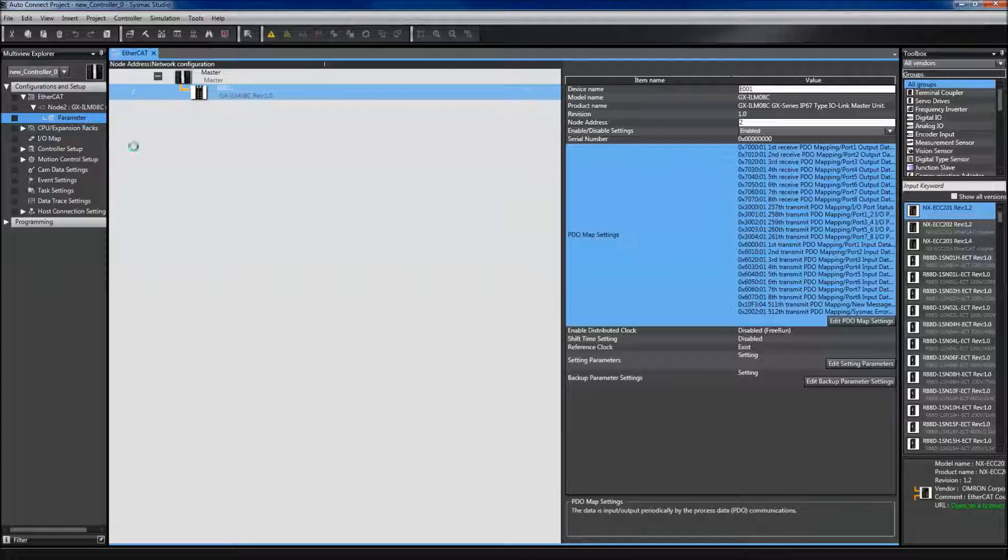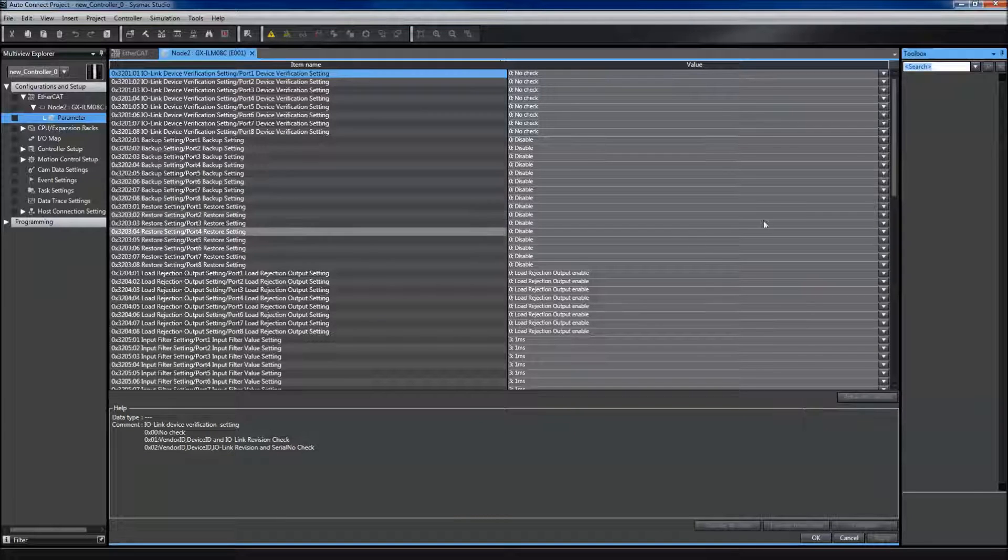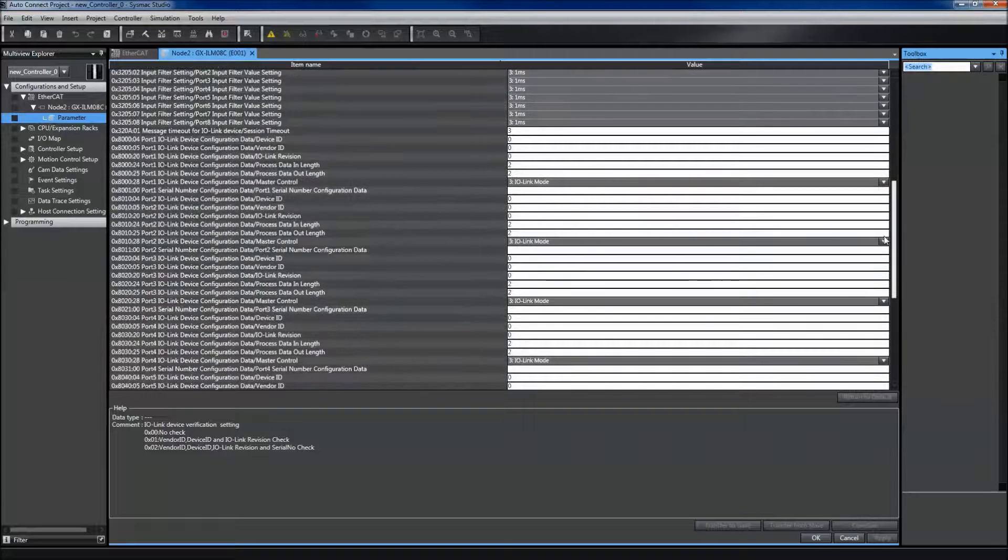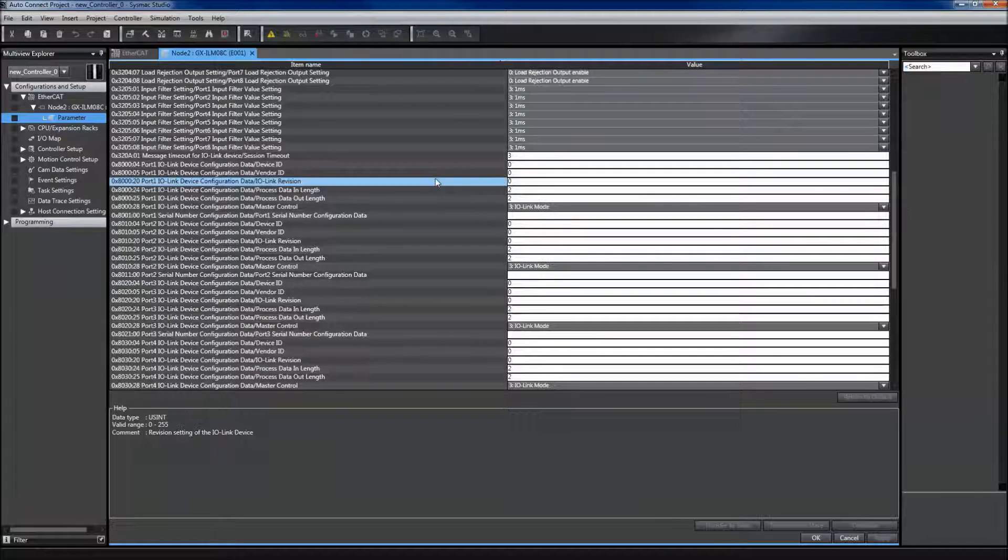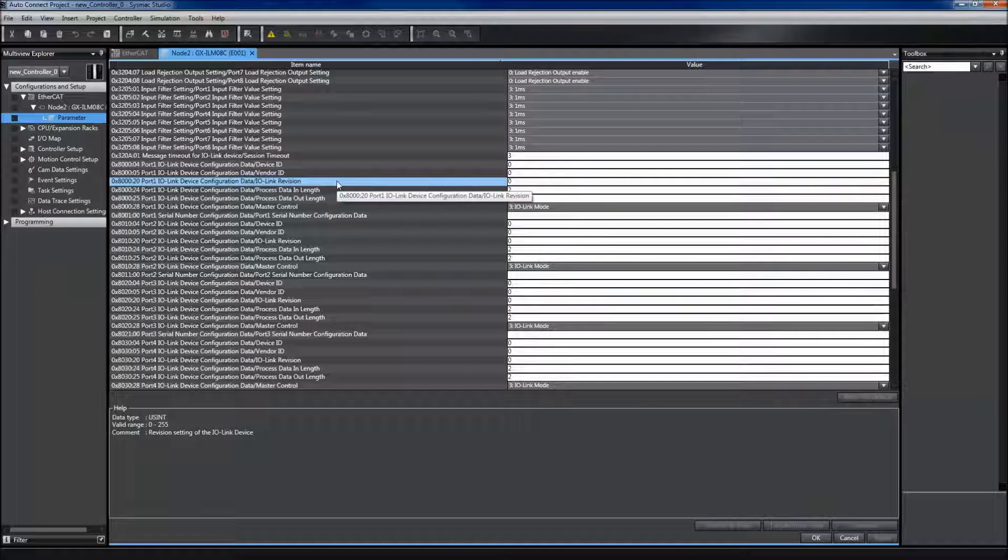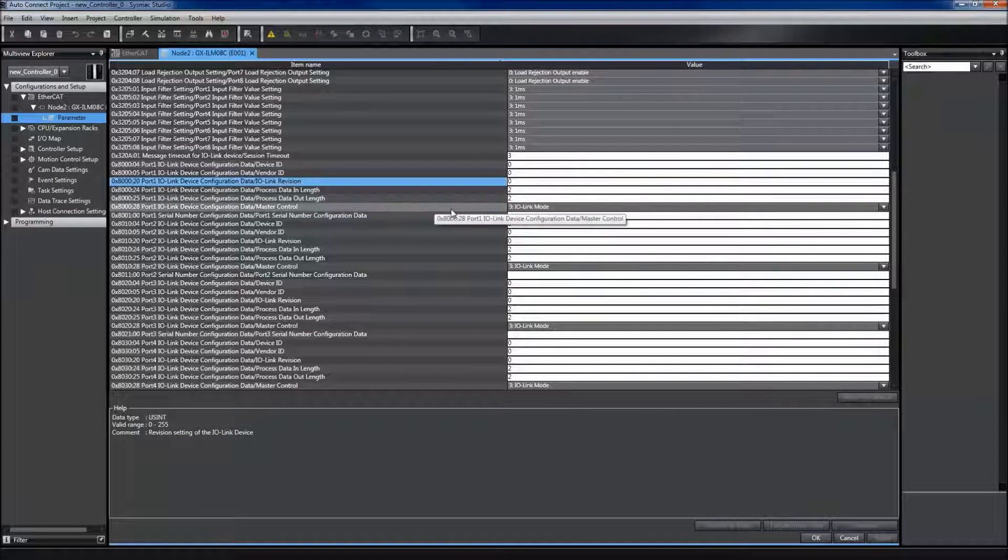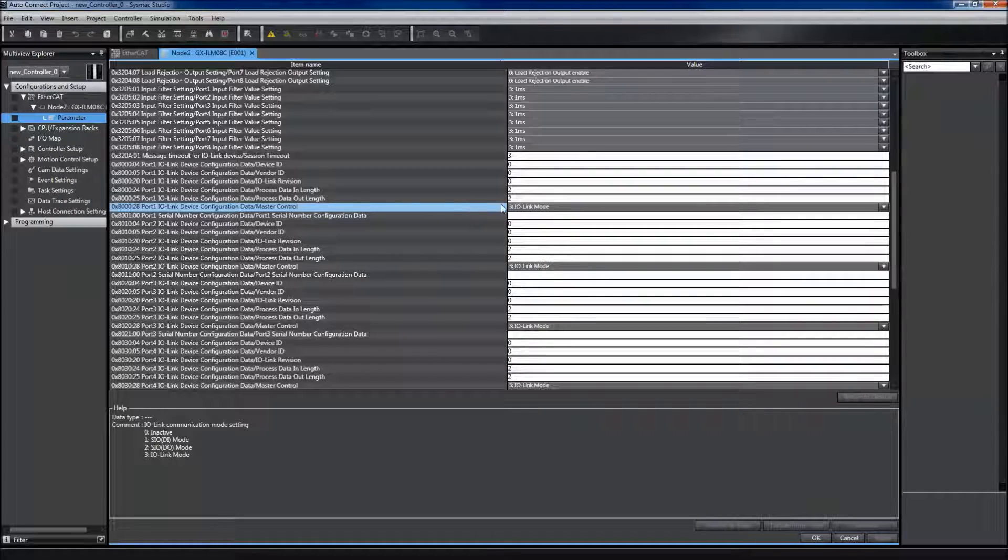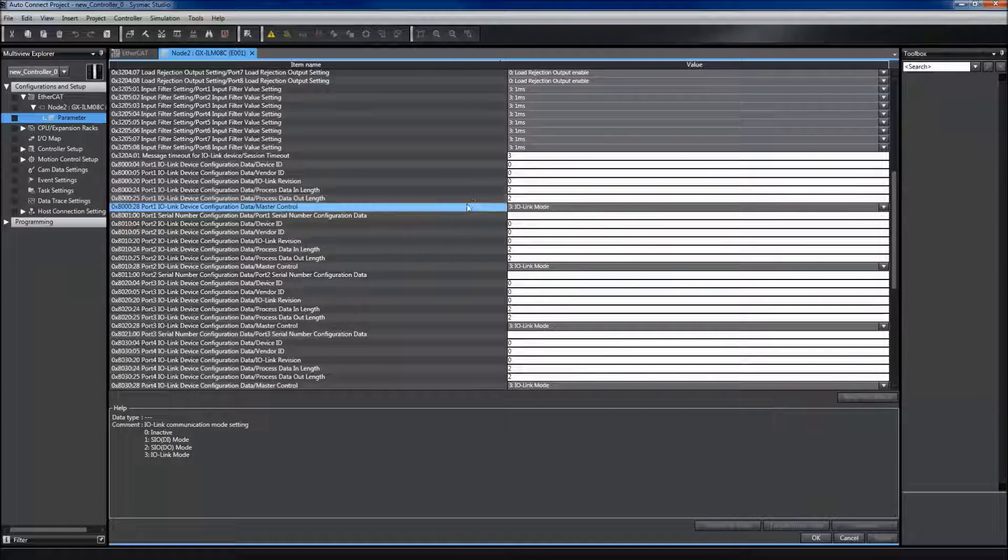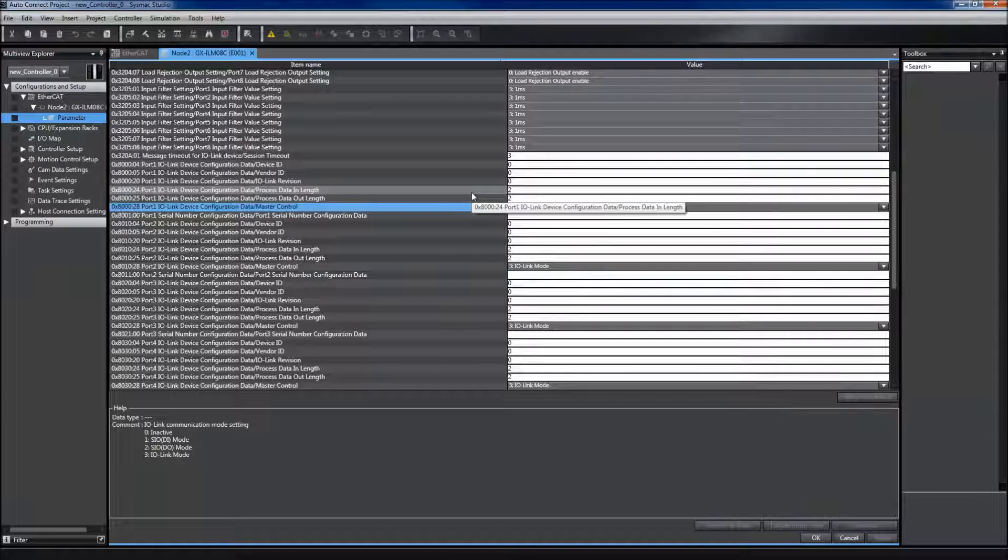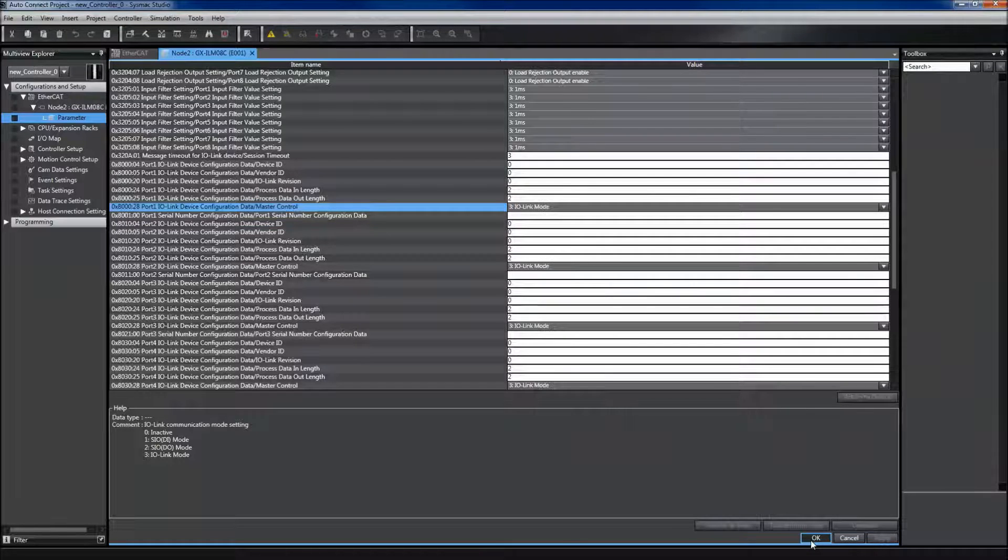I also need to double-check my IO-Link settings on the master. Since I have an IO-Link device attached to port 1, I want to make sure that it's in IO-Link mode. So I scroll down to port 1, IO-Link device configuration, and see that it does say IO-Link mode. The default is set for two bytes, and as long as it is not sending or receiving more than two bytes, this is okay and can remain as default.